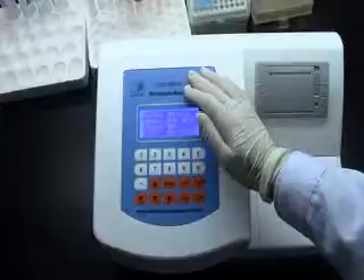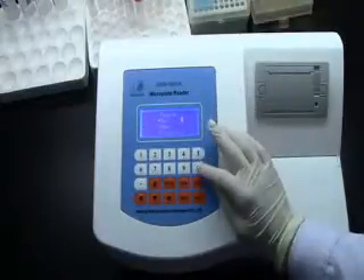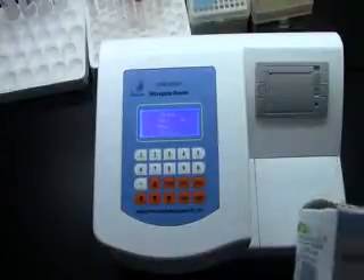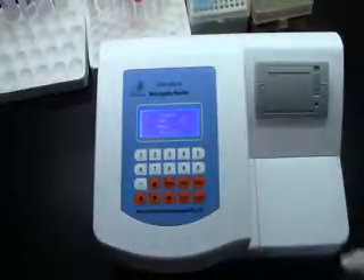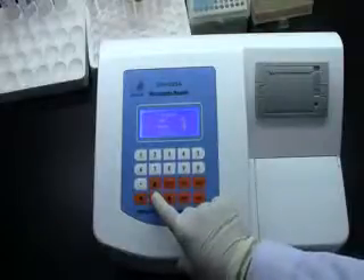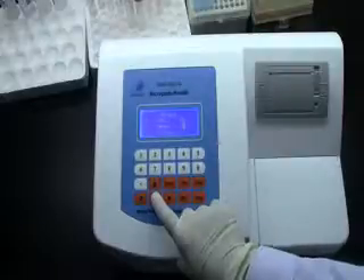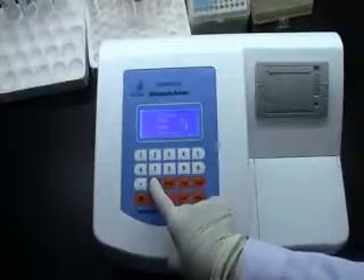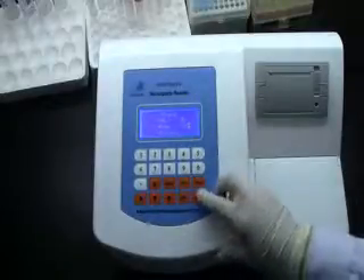Before we press the detect function, we should program first. So let's press 2 at the beginning. Program number — we can input, for example, 01. Press ENT to confirm. For the name, this microfilter reader is always used to test the bladder tumor-associated antigen using the ELISA method, for example. So we input the name BTAA. Press ENT to confirm.